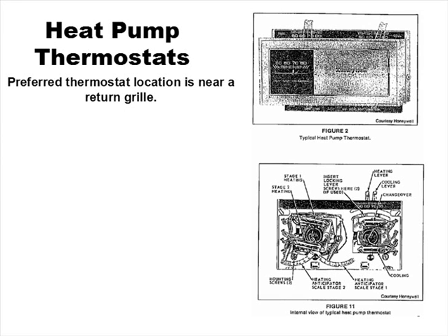that's the point of negative pressure in the room, and that's probably a good place to find the average temperature of the room. Because if you've got three or four rooms, five rooms, six rooms that are serviced by one central return, then the average temperature for all those rooms will be seen right at the entrance to the return grill. Because the return grill is the point of negative pressure in the area that the supply air will move to.